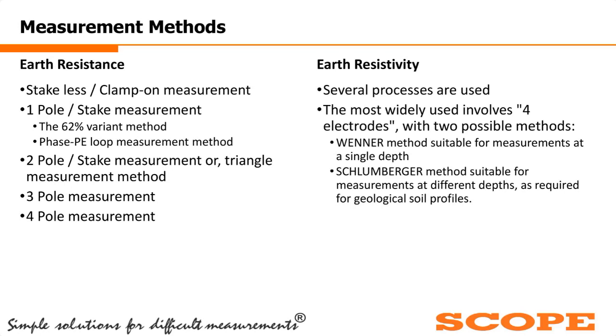The next one is the one pole or one stake method, in which two sub methods are there: the 62% method and the phase to phase earth loop measurement method. We will see these methods in upcoming slides. The next one is the two pole stake measurement or the equilateral triangle measurement. We will also see it in the next slides. Then the most popular methods, the 3-pole and 4-pole measurements, which are widely used for earth resistance measurement, we will also see in the next slide.